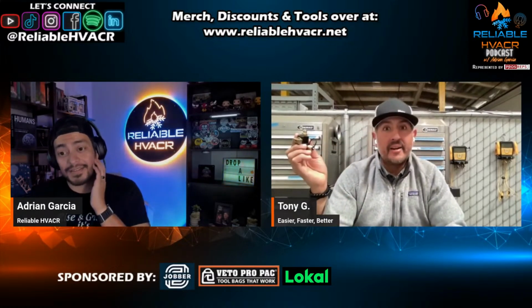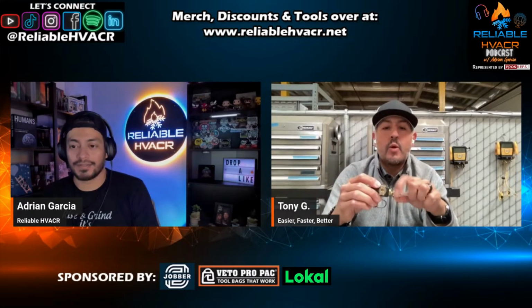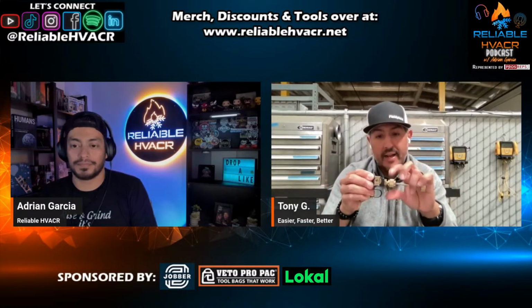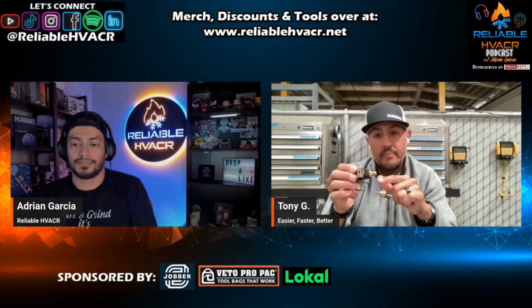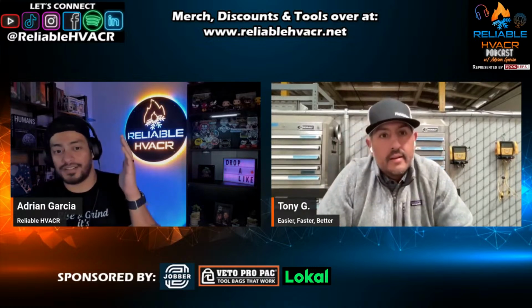And there's no shame there, right? No, it's just you can't see, you don't know. Yeah, exactly. So we thought, wow, how could we make it to where we can tell that we have gotten the valve core without having to disconnect? Because keep in mind, every time you have to disconnect this, A, you are using time, and B, you are dealing with a little bit of refrigerant that's coming out every single time, right? So we're doing it multiple times, it wastes time. And your sanity, just honestly.